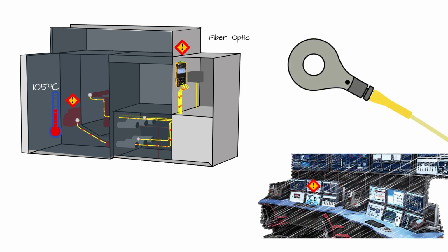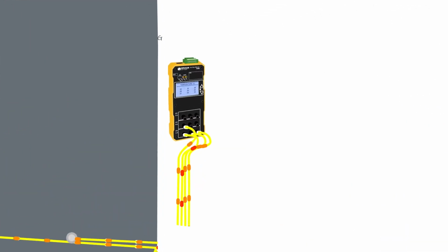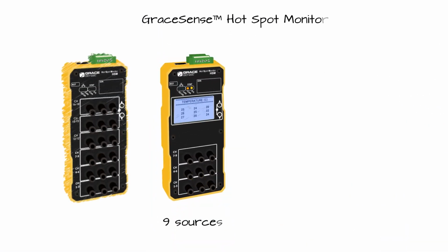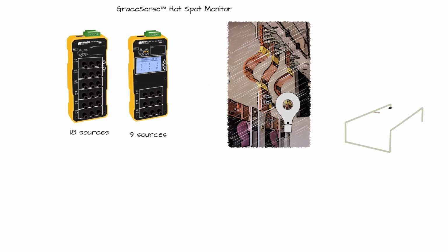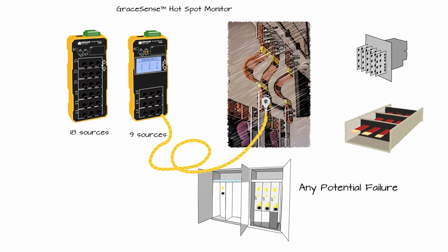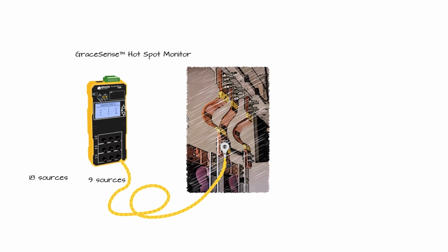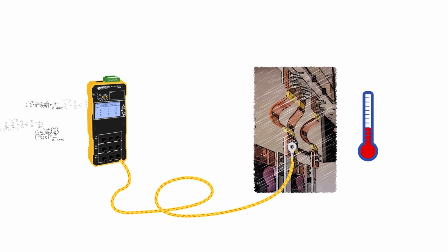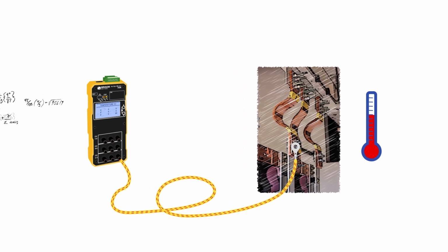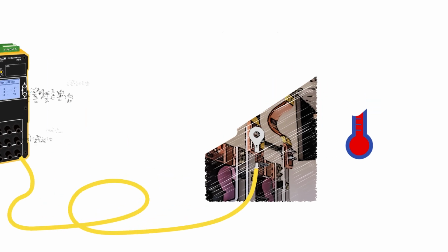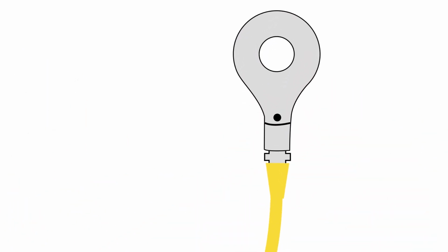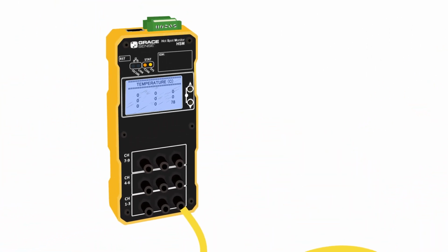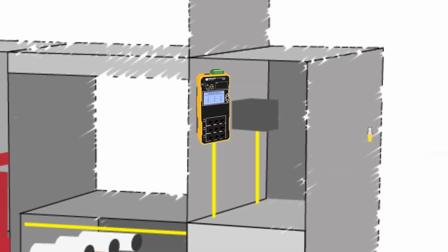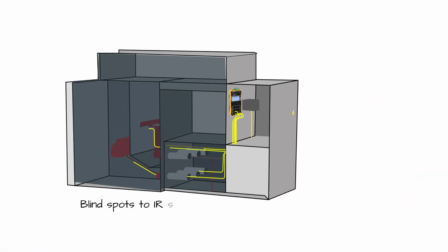The HSM utilizes patented fiber optic technology, providing constant temperature data available in 9 or 18 independent sources. The fiber probes can be mounted onto electrical bus bars, bus ducts, transformers, or any other source of heat. The Hotspot Monitor provides a unique combination of patented fiber technology and advanced algorithms that convert the change in light intensity to temperature. The patented fiber probes securely connect to a ring-style connector that conveniently mounts to the source of heat, while the other end connects to the HSM module. Sources of heat may include inaccessible equipment and blind spots to IR scanning.